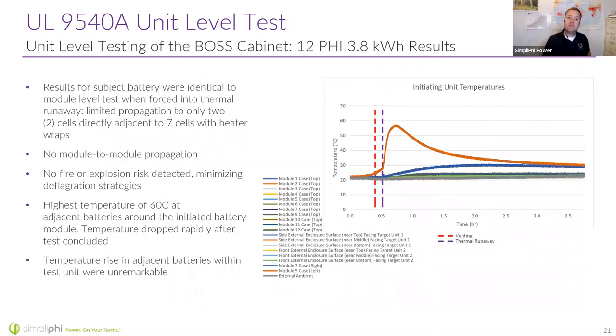These are the results. Really, the results were identical to what happened at the module level test. We had limited propagation to only 2 adjacent cells. There was no module to module propagation, no fire or explosion risk detected. The highest temperature we saw was 60 degrees, at thermocouple 56, the adjacent battery, and that temperature dropped off rapidly after the test concluded.